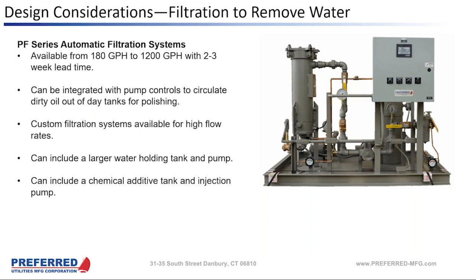The water was down at the bottom of the tank. Your sludge growth, your biological growth, is going to be a function of that water at the bottom of the tank, because it happens at the interstitial between the water and the fuel. And now that problem is happening all throughout the tank and maybe all throughout the system. And we've had systems where people have used water dispersing agents and then have had sludge grow in piping and valves. So just a word of caution on that.